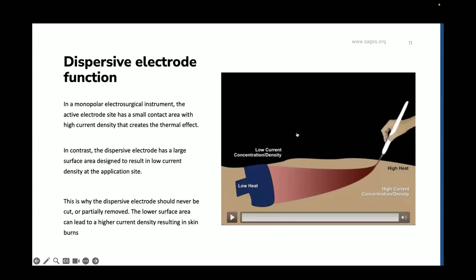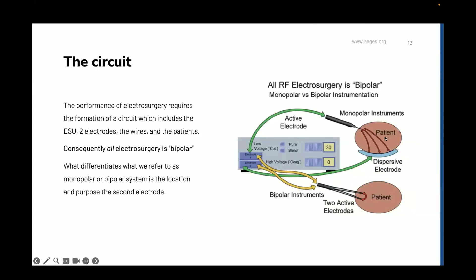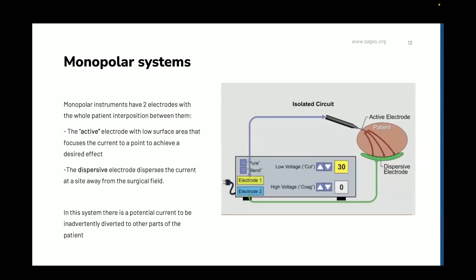So all radiofrequency electrosurgery is bipolar. Whether you're using bipolar instruments or monopolar instruments, you need two electrodes. The difference between the two systems is in a monopolar system, the two electrodes are separated and you have the whole patient in between. This can be advantageous and can allow more flexibility for the surgeon to deliver the current in ways that can lead to different tissue effects. But there's also an inherent risk where you can unintentionally deliver current to unintended parts of the patient, or the current can interact with other things such as pacemakers and such.